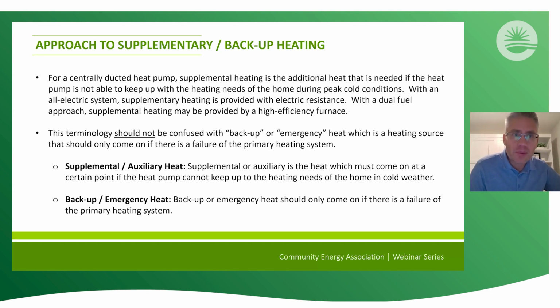Approach to auxiliary and backup heating. As Rob was hinting at earlier, for centrally ducted heat pumps, supplemental heating is the additional heat that is needed if the heat pump is not able to keep up with the needs of the home during peak conditions. With the newer types of heat pump technologies, the electric resistance heating can actually stage on in increments, so it's not necessarily pulling the full amount. That's a good benefit. But it's provided by electric resistance heating, so you lose the coefficient of performance. Instead of it being 3-to-1, it's just the 1 now.